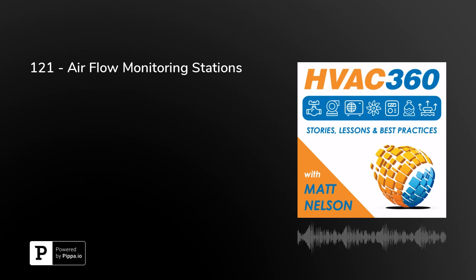So what are some of the lessons I've learned from airflow monitoring stations? Well, one of the things is that depending on the space constraints, you may be upstream or downstream. When we're talking about the outside air damper, you might be upstream or downstream of it. And what is that going to be, as far as turbulence? Are you far enough away from it? Where are you relative to the return fan? Is there a return fan? Are you close to the outside air opening? Are you going to get turbulence? That's ultimately what you want to understand, because if you have turbulence around a fan or around one of these flow measuring stations, like I said before, it's going to negatively affect the readings and the installation.